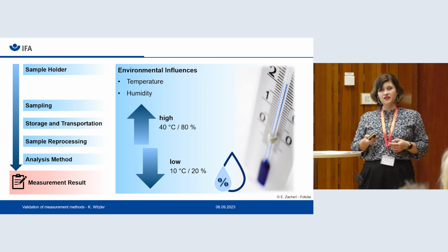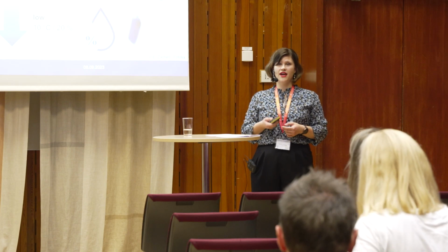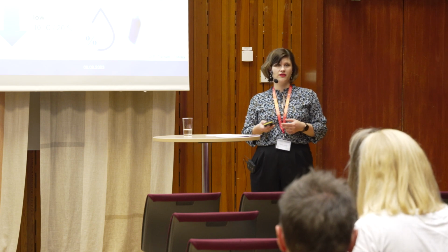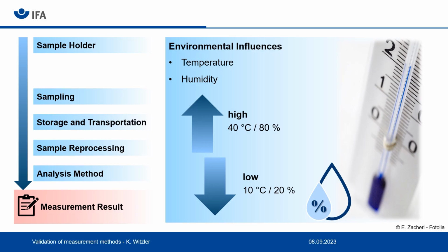But you have to test additional temperatures and humidities if you actually find these do have an influence on your sampling and your measurement results. You can also adjust these values if needed, if the use case of your method is higher or lower temperatures, so you can adjust this. These temperatures are not the only ones that need to be tested.